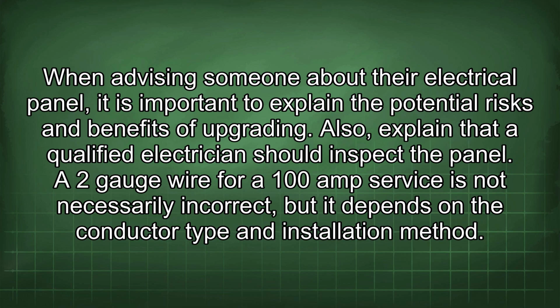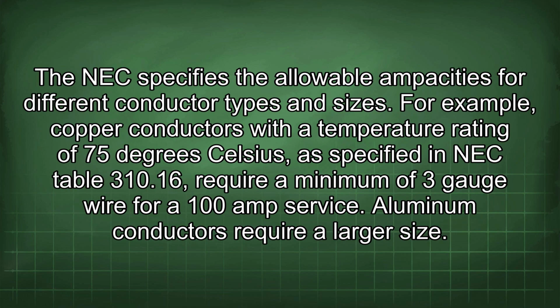A 2-gauge wire for a 100 amp service is not necessarily incorrect, but it depends on the conductor type and installation method. The NEC specifies the allowable ampacities for different conductor types and sizes. For example, copper conductors with a temperature rating of 75 degrees Celsius, as specified in NEC Table 310.16, require a minimum of 3-gauge wire for a 100 amp service. Aluminum conductors require a larger size.